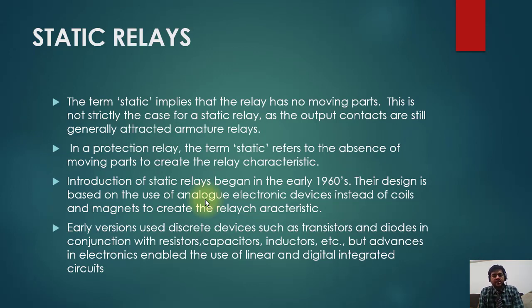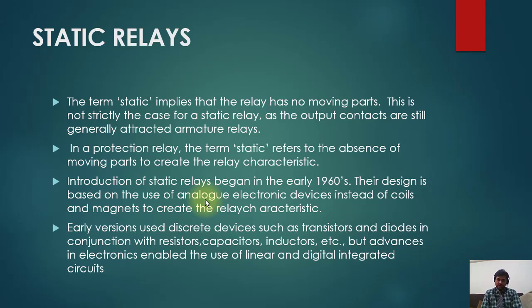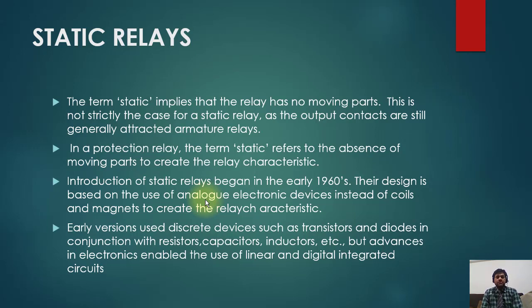The next step of relay evolution is static relays. The term 'static' implies that the relay has no moving parts, though output contacts are still attracted armature contacts. The term static refers to the absence of moving parts to create the relay characteristics. The introduction of static relays began in the early 1960s. Their design is based on the use of analog electronic devices instead of coils and magnets to create the relay characteristics.